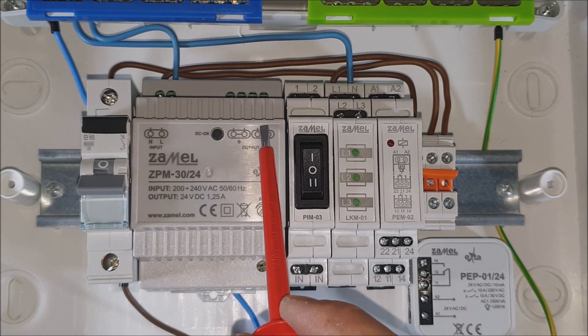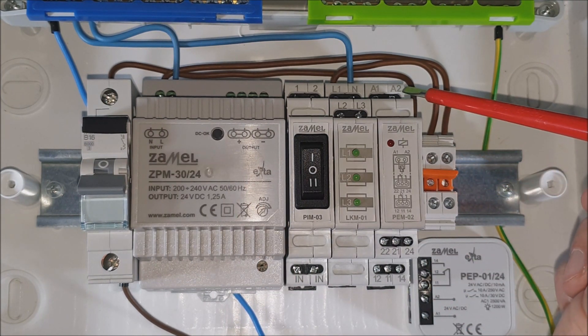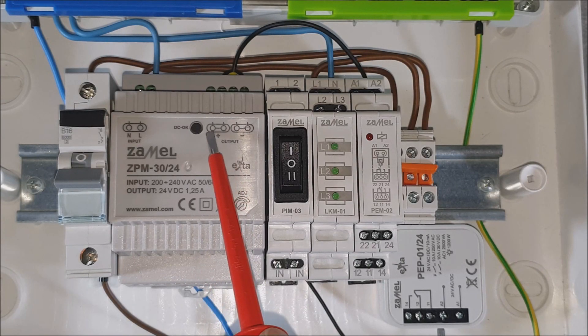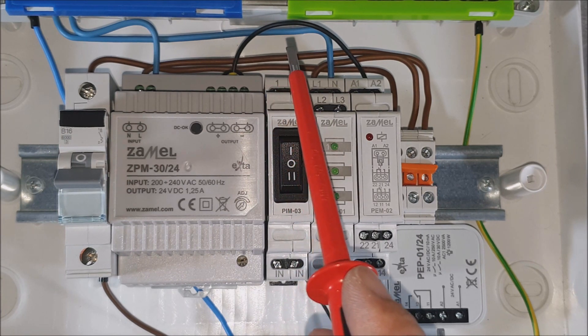The negative potential of 24 volts DC coming from the ZPM-30/24 power supply goes both to terminal A2 of the PEM-02 relay and to the PEP-01024 flush relay. The positive potential of 24 volts DC from the terminal marked with the sign N-plus of the ZPM-30/24 goes to the input terminal of the double circuit switch PIM-03.